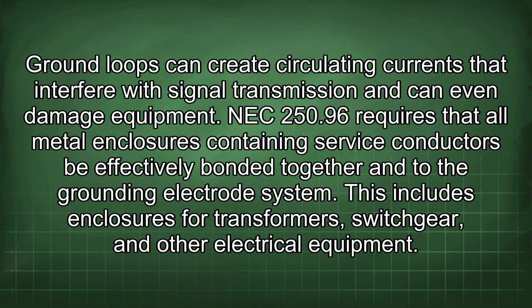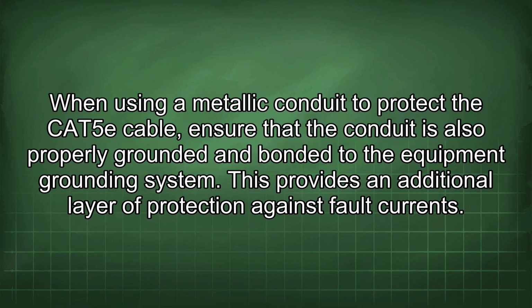NEC 250.96 requires that all metal enclosures containing service conductors be effectively bonded together and to the grounding electrode system. This includes enclosures for transformers, switchgear, and other electrical equipment. When using a metallic conduit to protect the CAT5e cable, ensure that the conduit is also properly grounded and bonded to the equipment grounding system. This provides an additional layer of protection against fault currents.